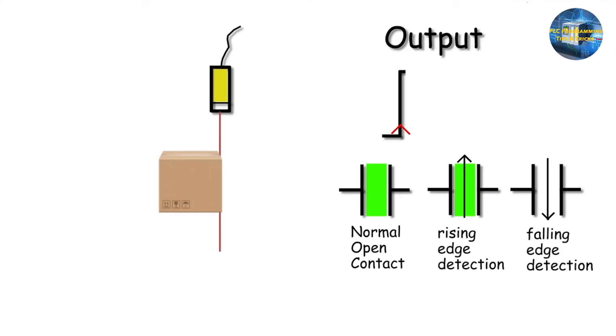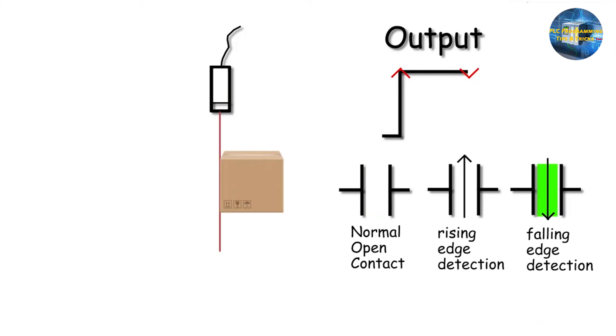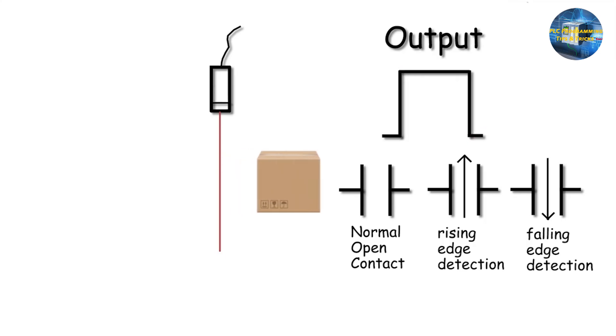The normally open contact will remain closed as long as the box is in front of the sensor. In this way we can detect precisely when the sensor output signal turns on. When the box leaves, the sensor output signal goes off, but the falling edge detection contact will be turned on for one scan cycle, then turned off in the next — this is how we detect when the sensor output turns off.